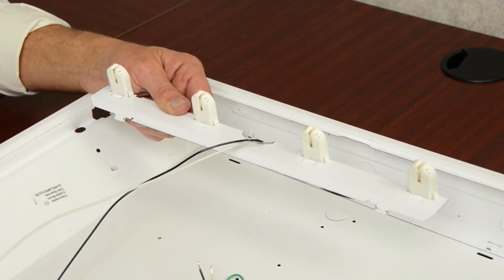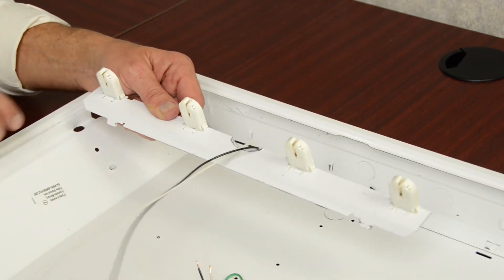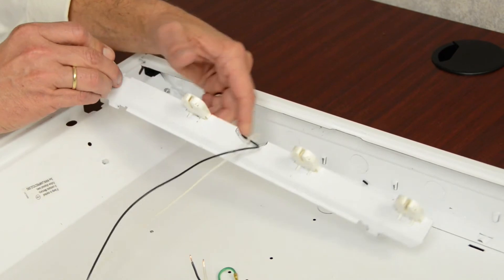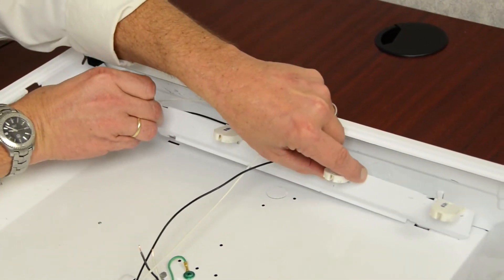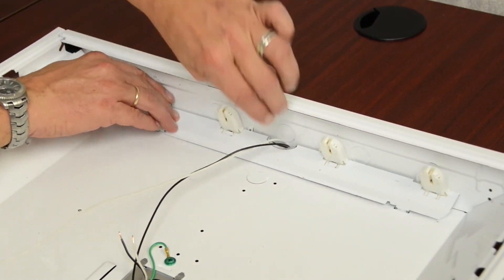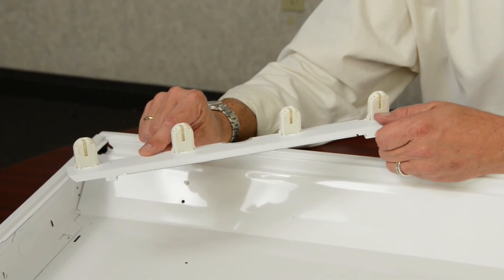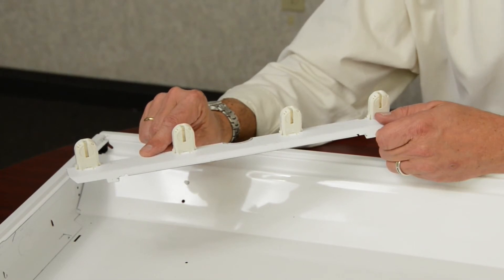With the new non-shunted sockets now installed into the socket bar, we're ready to replace the socket bar back into the fixture. We have also installed new non-shunted lamp holders in place of the old existing shunted lamp holders on the non-powered end of the fixture. At this point, these lamp holders are exactly that — just lamp holders, as the LED tubes are powered from just one end.